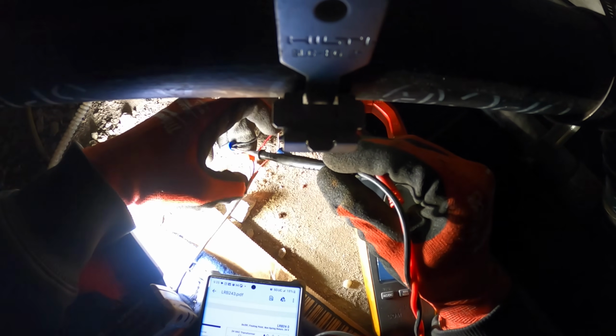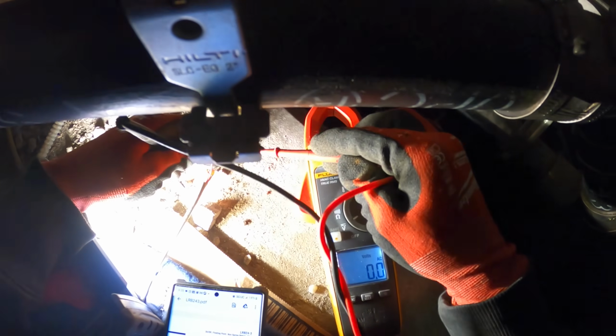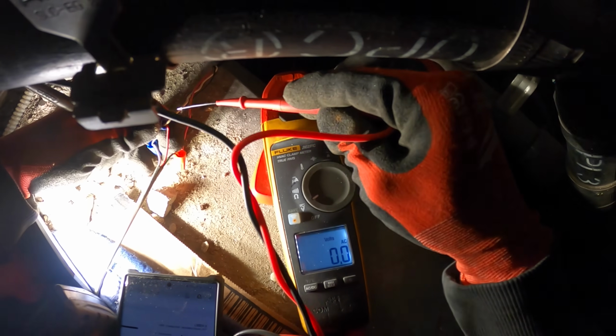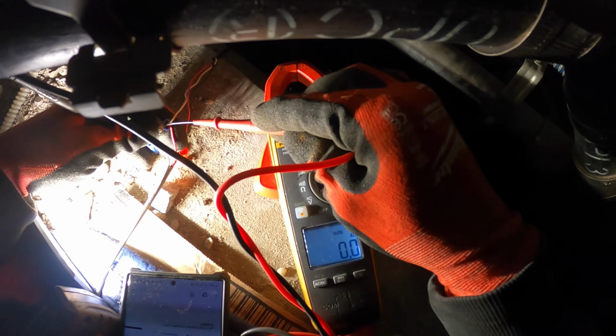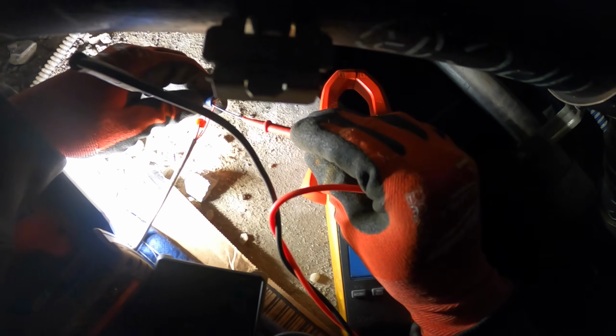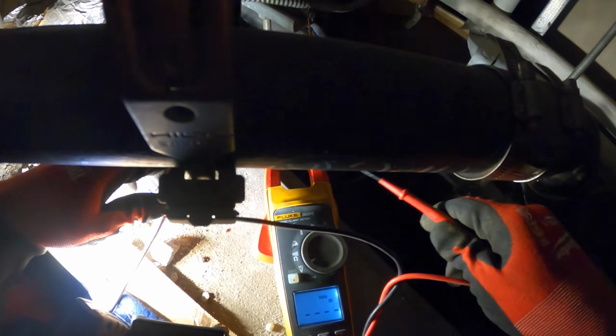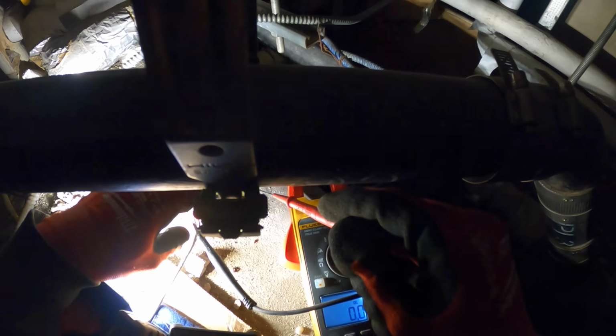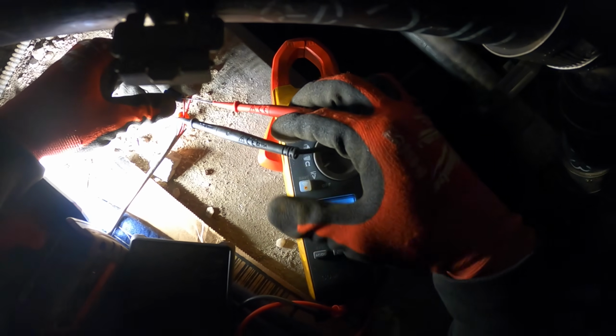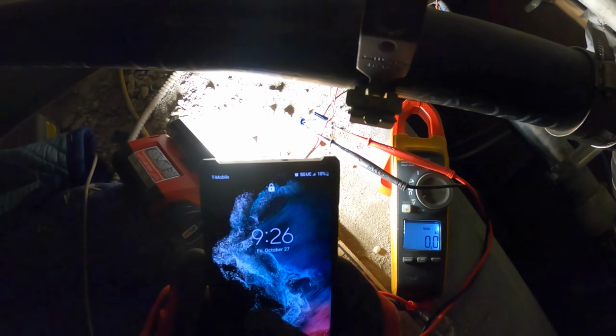Then I'm gonna check between common and white, the next one. Okay, just making sure we're actually getting a connection. Nothing is there. I'm also gonna switch now to DC volts between common and Y. No DC voltage. Switch it back to AC, 0 volts there. Let's call Christian, see if he can switch over.